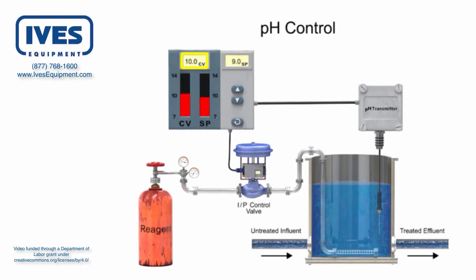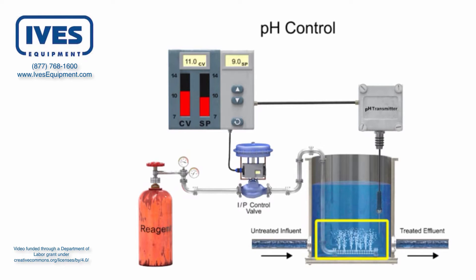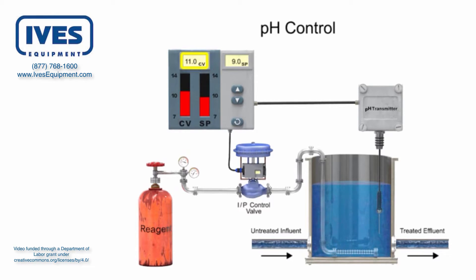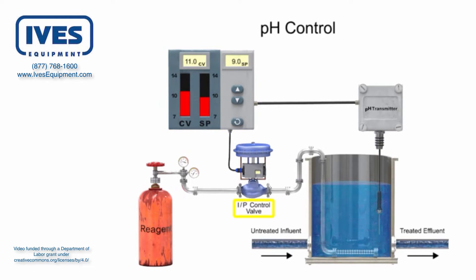If the values are not equal, the controller sends a signal to the control valve that applies carbon dioxide to the tank. The reagent is applied to the tank at varying rates to precisely control the pH level. With the pH level at 11 detected by the sensor, the controller commands the control valve to open and introduce more carbon dioxide.